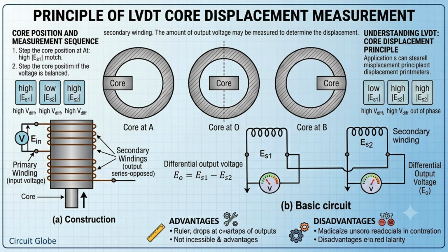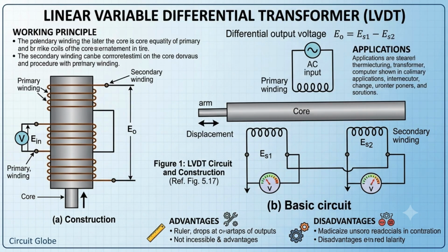The residual voltage may be due to magnetic unbalance or electrical unbalance. The presence of harmonics in the input supply voltage produces harmonics in the output voltage because of saturation of the iron core. It also contributes to residual voltage. Stray magnetic fields may also cause residual voltage, which may be overcome by using a magnetic shield slotted longitudinally.